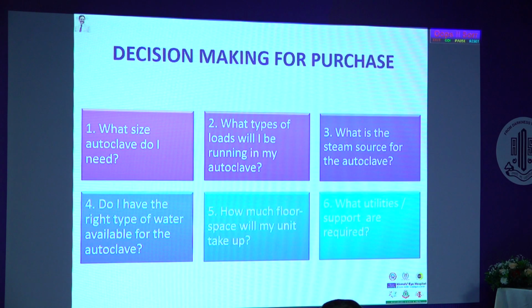Floor space - autoclave is always a heat sensitive equipment. Leave at least 2 feet of space around your autoclave. It's very, very important for maintenance. Very often staff get injured or get burnt because of very close space.